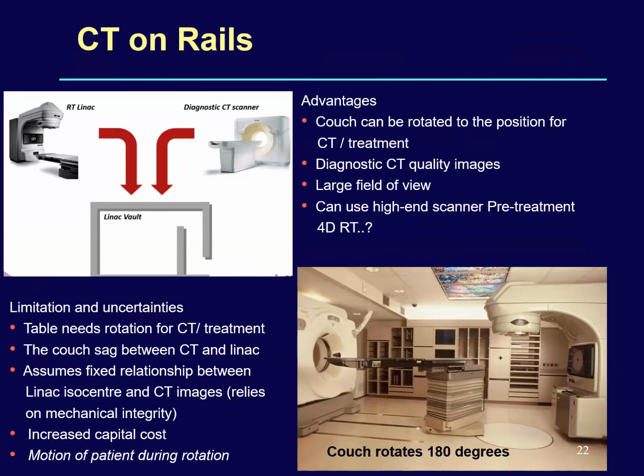The other option explored initially for volumetric image guidance was having a LINAC and a diagnostic CT unit inside the same bunker, installed opposite to each other, with a couch shared between both units. After doing a CT and checking whether the position is reassured, you rotate the couch 180 degrees with respect to the LINAC isocenter, then do the shifts if needed, and then treat the patient. The advantage is that it can offer diagnostic quality.